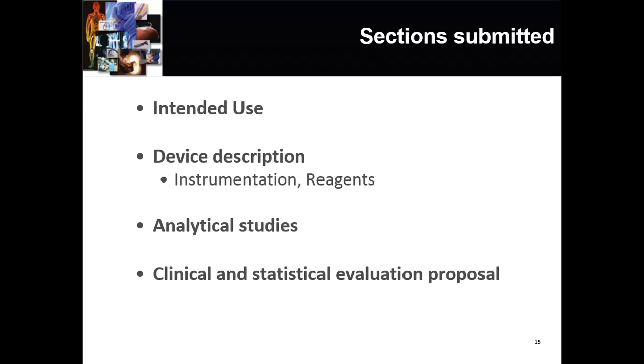They also had to develop a device description, and that is also a great homework assignment to figure out how do you describe a device, and how much do you describe, to what level of detail. Then they described the hypothetical analytical studies that were done on this hypothetical device to characterize it, and then finally came up with a clinical and statistical evaluation proposal.